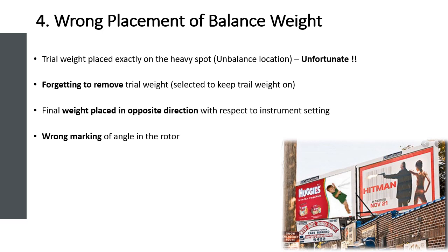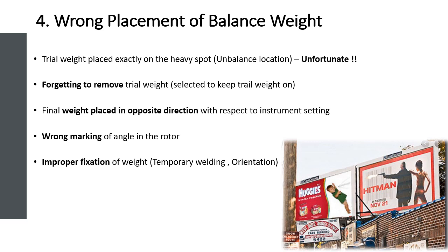Manual errors while marking the rotor can occur when counting blades or support locations, leading to wrong markings. Improper fixation of weight is also an issue — this includes the welding mass added during temporary welding, and ensuring temporary welds are reinforced once balancing is complete. The orientation of the balancing mass must be such that it does not disturb the process flow and cannot be removed easily.